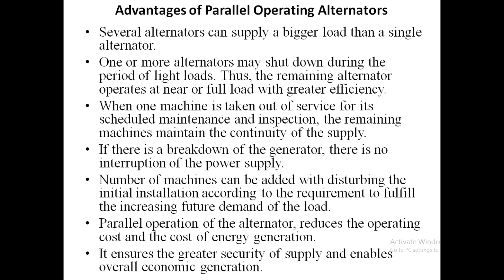Now there are some necessary conditions for this parallel operation. One condition is the terminal voltage, that is, the rated voltage. Normally we specify the voltage rating of an alternator, like a 3-phase 415 volt 50 Hertz alternator operating at a power factor of 0.8. Whatever voltage is specified, that is the terminal voltage V. The voltage of all the alternators connected in parallel should be the same. If an alternator is connected in parallel with another alternator, the terminal voltages of both machines should be the same. Or if it is connected with an infinite bus bar, then this alternator should have a terminal voltage the same as the bus bar voltage.